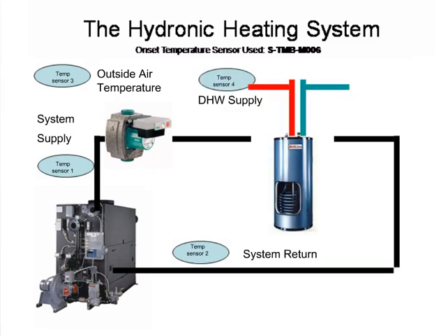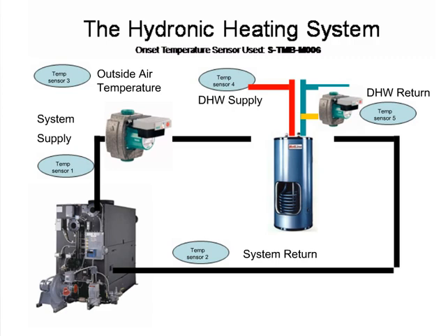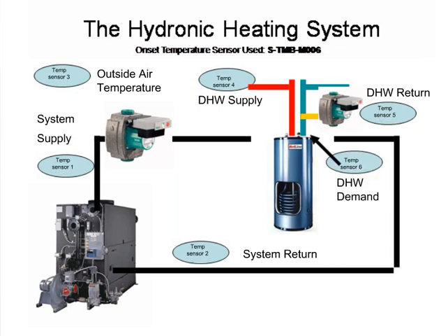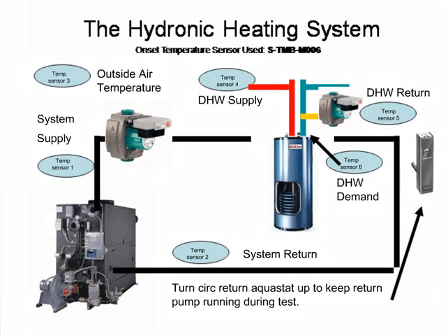We also need to monitor domestic hot water heating system demand. The domestic hot water supply sensor will indicate any shortages occurring during peak demand periods. We also monitor the circulation return to see the differential the domestic hot water system sees during non-demand periods, or standby losses. An additional sensor can be placed to watch real-time domestic hot water demands to see if they fall within a normal load profile. If the circulation return pump is normally controlled by an aquastat, it is necessary to turn the aquastat up to keep the pump running constantly during this test. Once the test is done, remember to return the aquastat back to its normal setting.